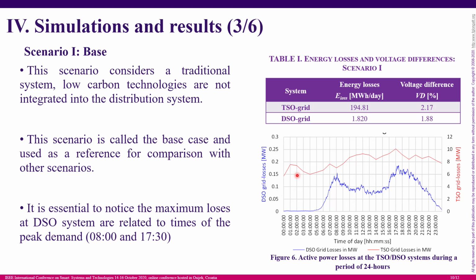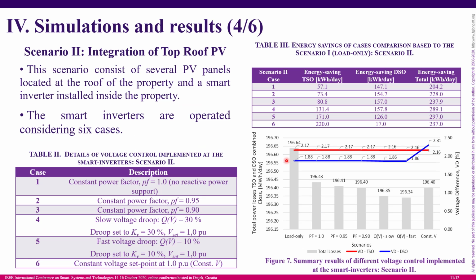Okay, here you can see the 24-hour profile for the grid losses in megawatts, and as you can see, the DSO losses change following basically the load profile. However, the TSO grid losses are only slightly different, because there are some other loads considered inside the network. Okay, scenario number two includes the integration of rooftop PV systems, and here we have enabled the PV inverters with 6 different controllers: constant power factor 1.0, constant power factor 0.95, constant power factor 0.9, then 2 voltage droops, one that we call a slow voltage droop and one called fast voltage droop. And finally, we have the ideal case, which is the constant voltage set to 1 per unit.